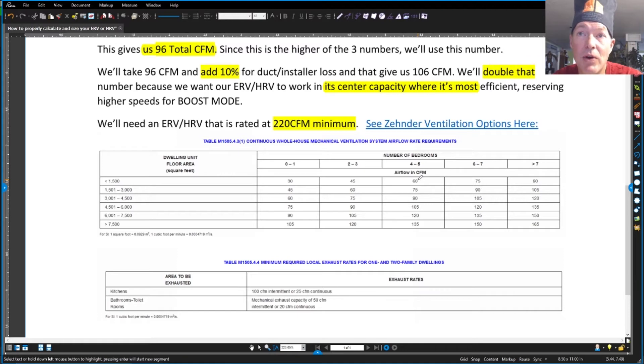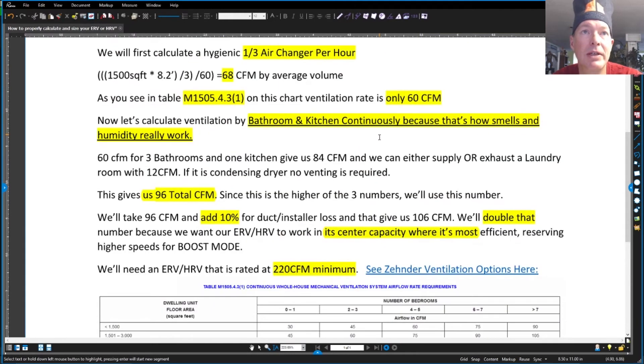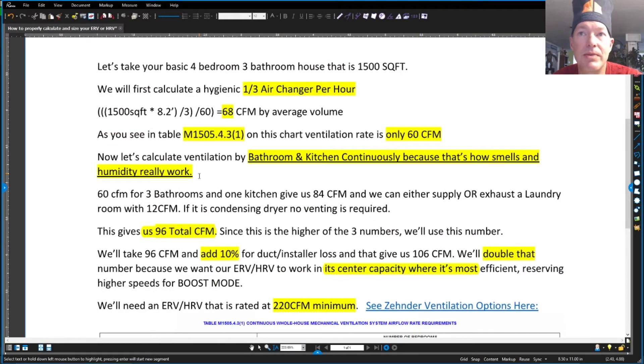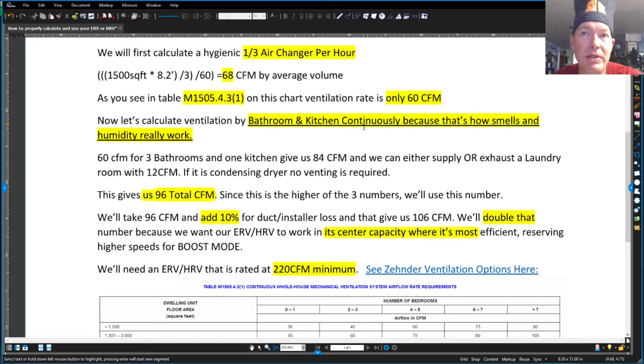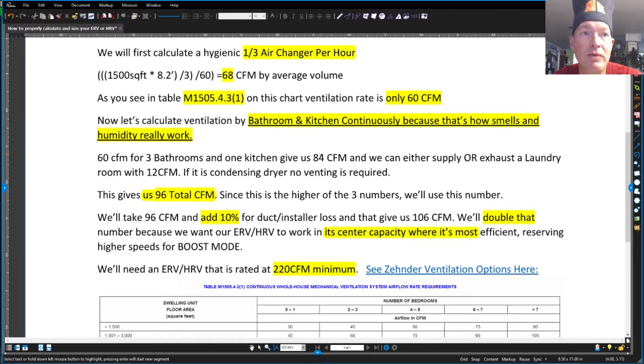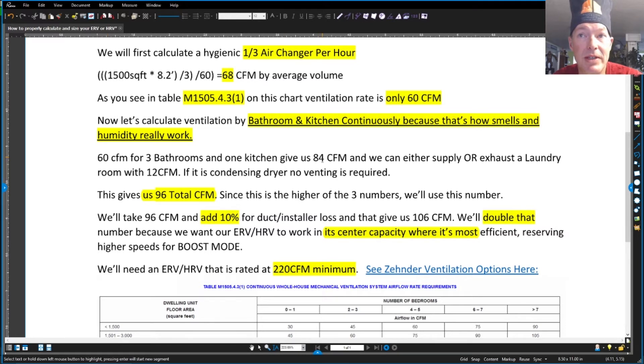And that's really all the requirements you're looking for in this table. However, Passive House methodology and practice is known to be much cleaner, and this is where the delta lies. If we're looking for continuous bathroom and continuous kitchen exhaust, we'll take 20 CFM for each bathroom and then 24 for the kitchen. So that 60 CFM gives us 84 CFM.